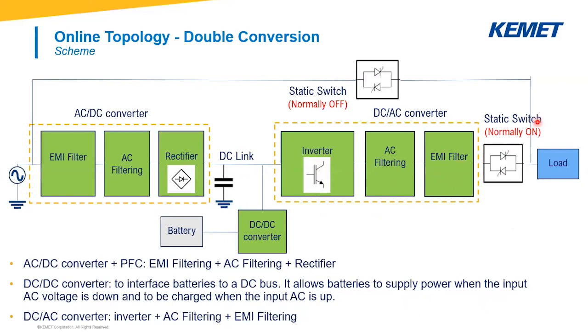After that, we have the DC-AC converter stage made up of an inverter, an AC filtering stage, and an EMI filtering stage. At the end of the UPS we have static switches. During normal operation, one switch is normally on because power comes from the inverter. But it could happen sometimes that the UPS can be totally bypassed — in this case that switch goes off, another goes on, and the load is connected directly to mains.